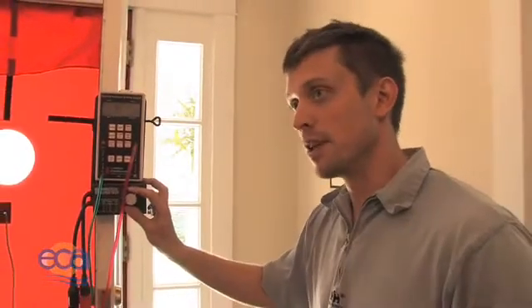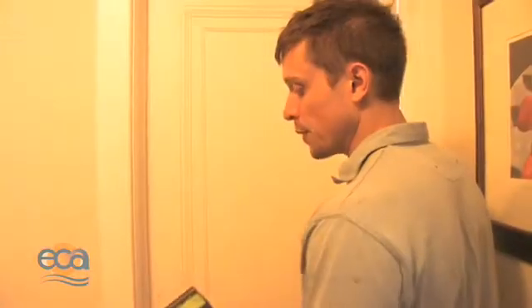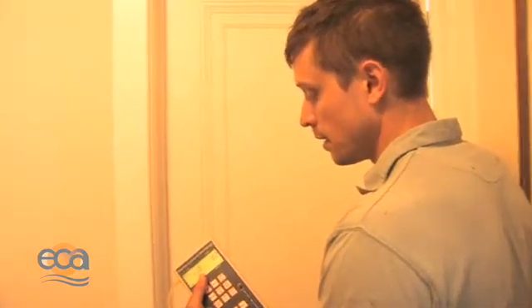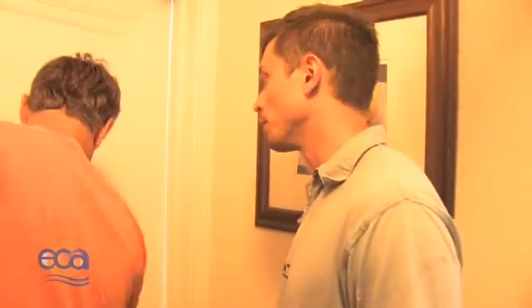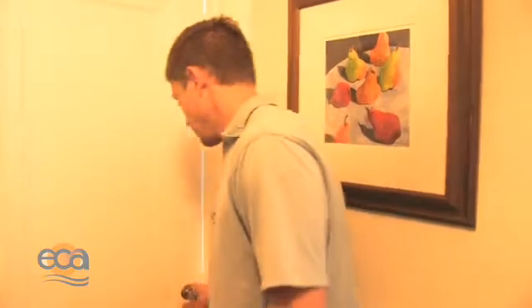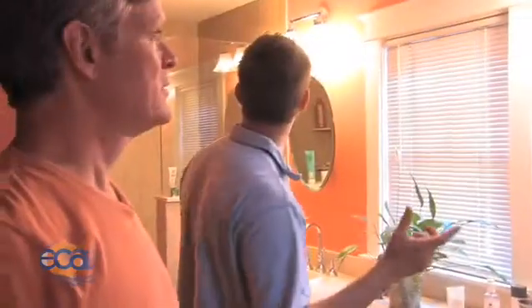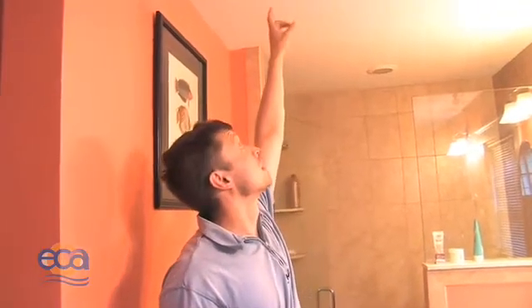Let's have a look around and see if we can pinpoint some of the air leaks in your home. There's quite a bit more air moving from this room in the basement, and you're also pulling from the bathroom, which has a vent. You can really feel the air gushing. So we're pulling air in somewhere — there's more opportunity in here. Here's a common problem: recessed lights. You can kind of smell the attic now, so we're definitely pulling in attic air. The idea would be to get a better cover on top of these things from the attic space.